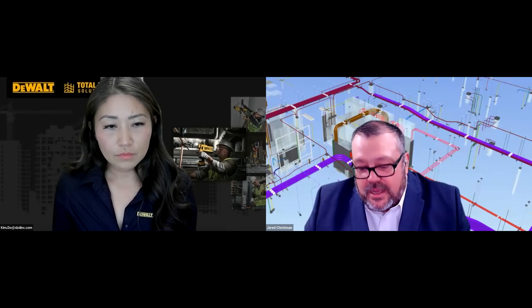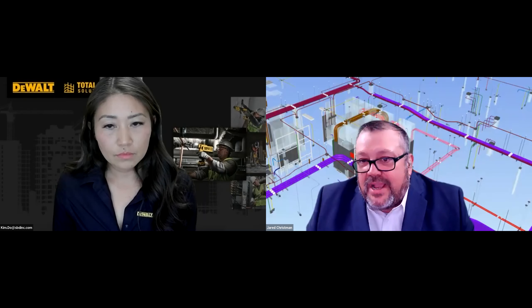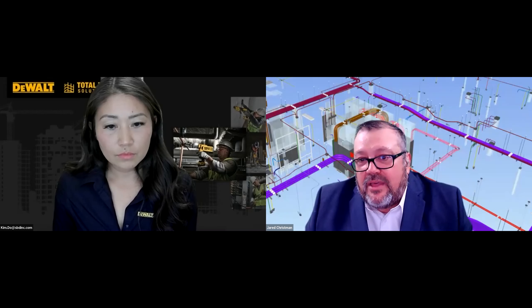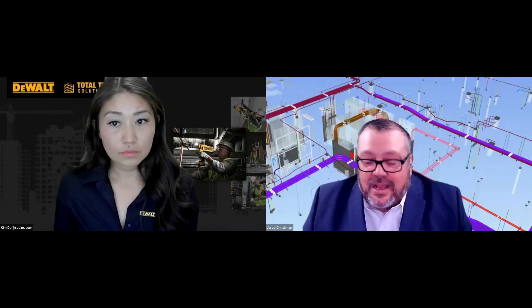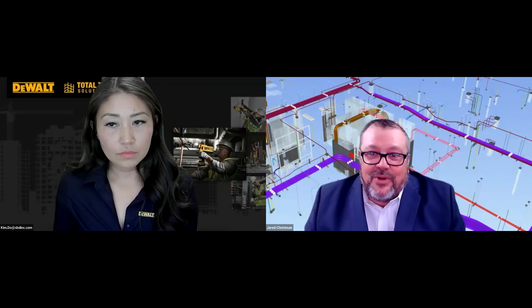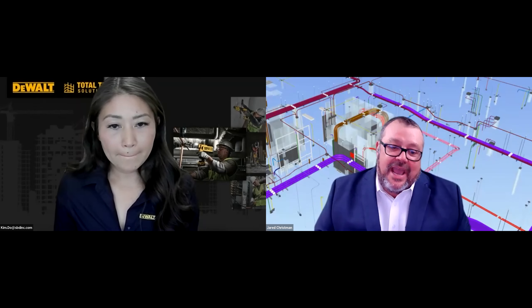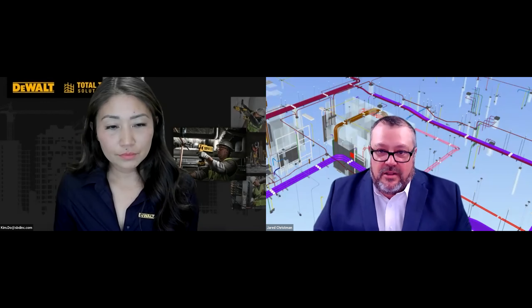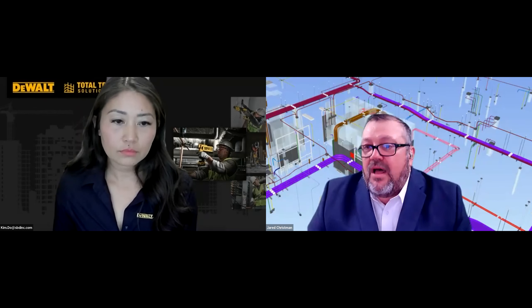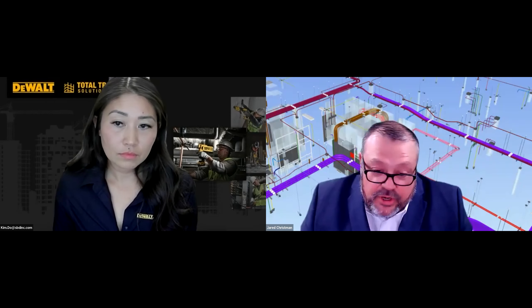As we started going through the modeling aspect of it, we started to incorporate in-wall. We could see where our next device was, see if there were any issues or items we needed to move around windows. Once we incorporated the model, we took that 20 to 25-foot blanket length and started to just add 15% on top of whatever is in the model as a little buffer. Before the BIM process, we were using prefab assemblies — it was just a little more rudimentary.